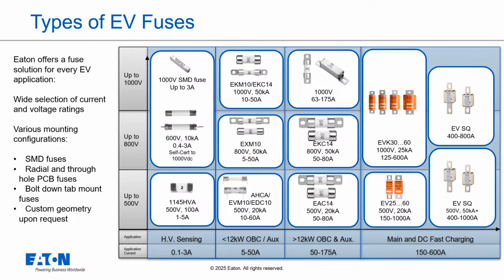These fuses come in various voltage ratings too, from 500 volts up to 1,000 volts. Different current and voltage ratings are available, often with overlapping sizes to give designers flexibility. Mounting options are also varied, including surface mount, radial or through-hole for PCBs, and larger bolt-down tab mounts. Some manufacturers like Eaton even offer custom geometry if needed.